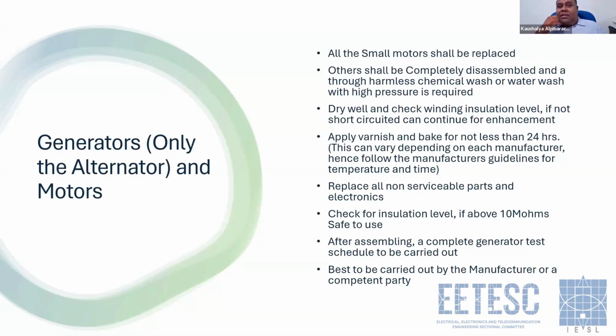because that may precisely tell you what type of varnish you are going to use, what the temperature set point of your oven is, and what the duration of your drying or baking process is. Replace all non-serviceable parts and electronics. Check the insulation, and if above 10 mega ohms, yes, you are safe to use. After assembling, a complete test for motors or generators will have to be carried out.